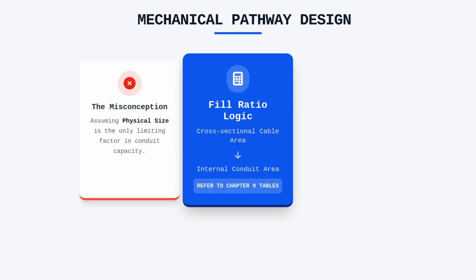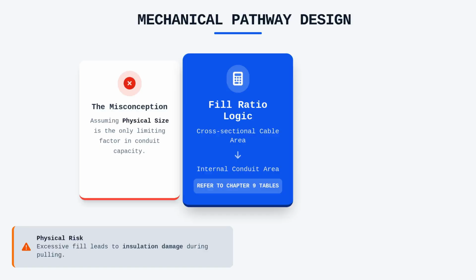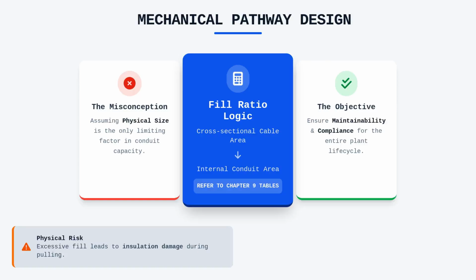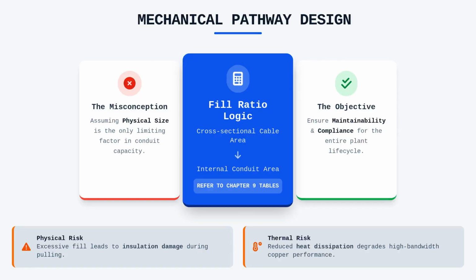If you pack a pathway beyond these percentages, you risk damaging the cable insulation during the pull and interfering with future maintenance. Additionally, we must consider the heat dissipation capacity of the conduit, which decreases as the fill percentage increases, potentially impacting the performance of high-bandwidth copper links. By strictly calculating these fill ratios, you ensure that the installation remains maintainable and compliant for the life cycle of the telecommunications plant.